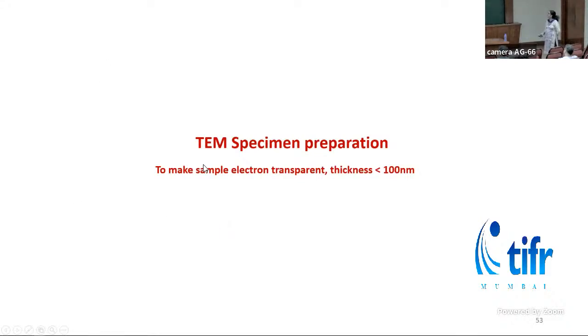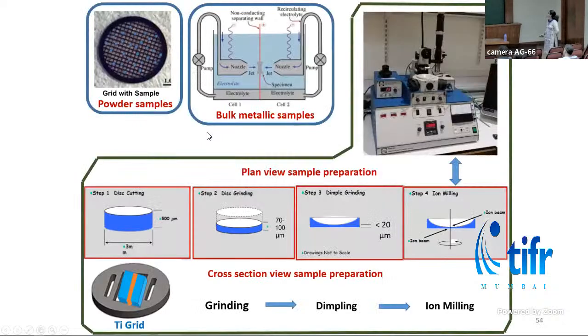As I mentioned earlier, TEM sample preparation is a very tedious job. Here, the job is to make the sample electron transparent, and the thickness should be less than 100 nanometer. If we have a powder sample, we can simply sonicate it in a suitable solvent and then put a drop on a carbon grid. If we have a bulk metallic sample, it can be prepared by etching with electrolyte. There is an electrolyte bath, a suitable electrolyte is selected, and there are fine nozzles. The sample is first thinned down to 100 micron, and it is mounted vertically in this bath, and electrolyte is sprayed by these nozzles, which makes the sample electron transparent.